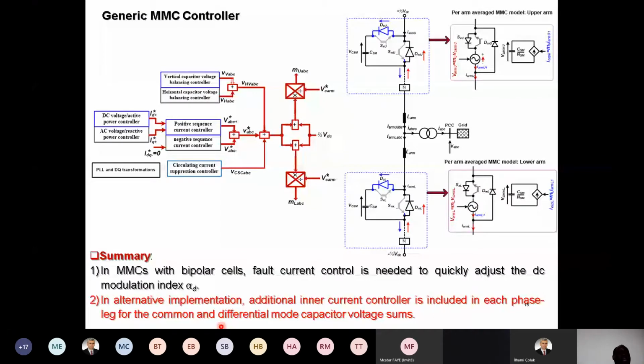And here is a generic control system for the MMC, where this part is similar to a conventional two-level converter, which is in the outer loop. You have either DC voltage controller or active power, and here you have AC voltage or reactive power. So if you use DQ, if your D axis is aligned with the voltage, which means any components in line with the voltage are active power components, and any component which is 90 degrees to the voltage is reactive power. So in the D axis, in the outer loop, I have DC voltage or active power, and in the Q axis, on the output, I have AC voltage or reactive power.